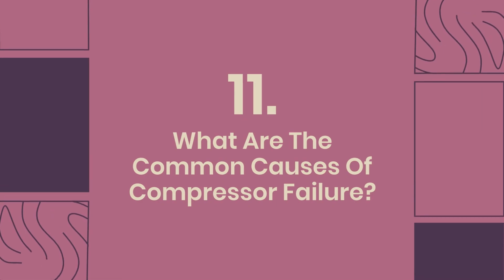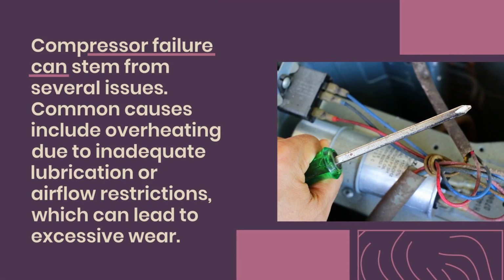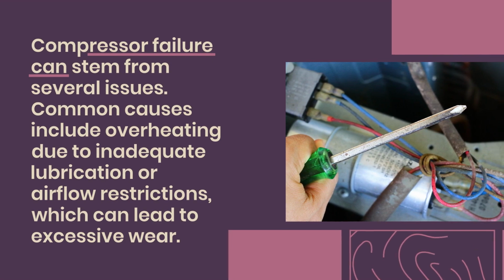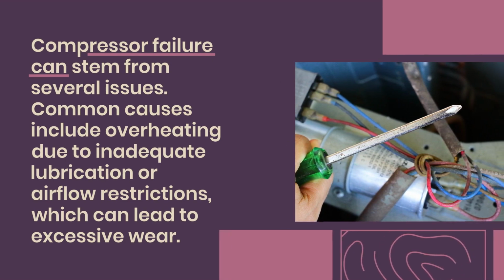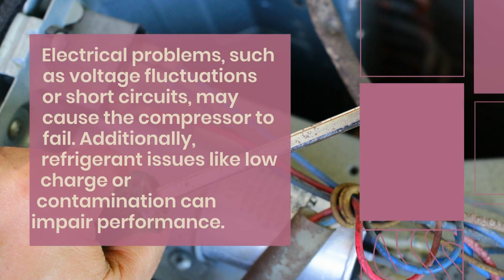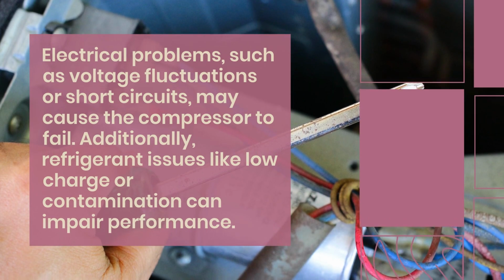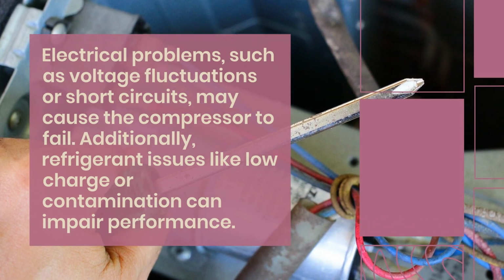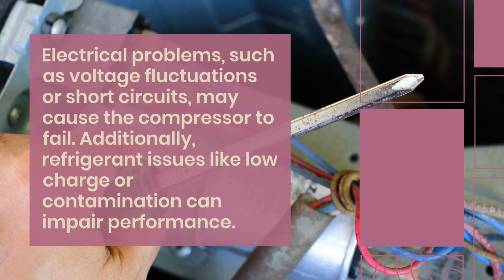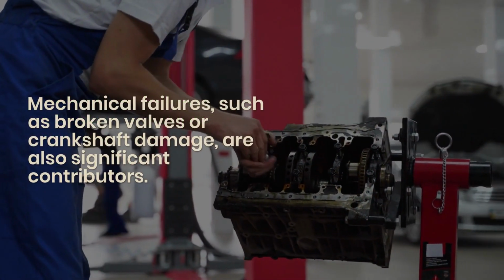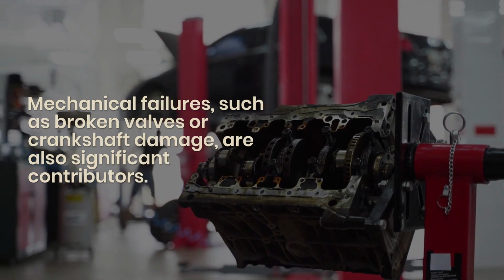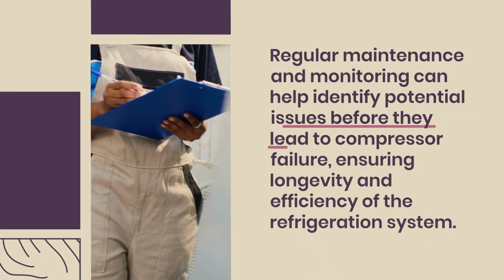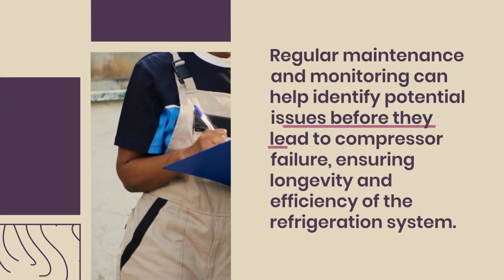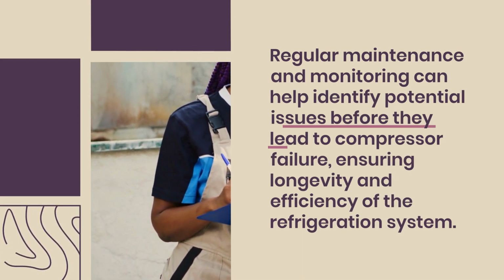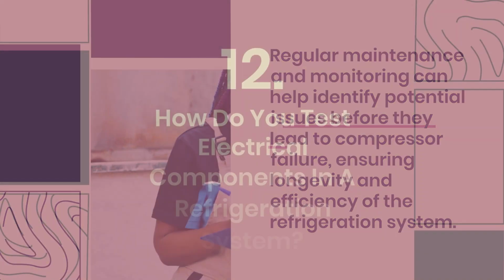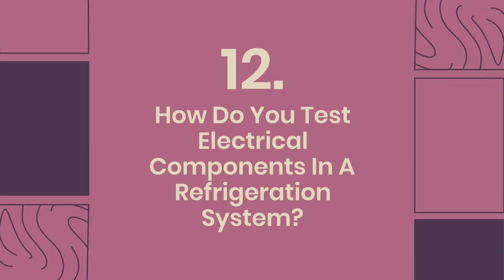11. What are the common causes of compressor failure? Compressor failure can stem from several issues. Common causes include overheating due to inadequate lubrication or airflow restrictions, which can lead to excessive wear. Electrical problems, such as voltage fluctuations or short circuits, may cause the compressor to fail. Additionally, refrigerant issues like low charge or contamination can impair performance. Mechanical failures, such as broken valves or crankshaft damage, are also significant contributors. Regular maintenance and monitoring can help identify potential issues before they lead to compressor failure, ensuring longevity and efficiency of the refrigeration system.